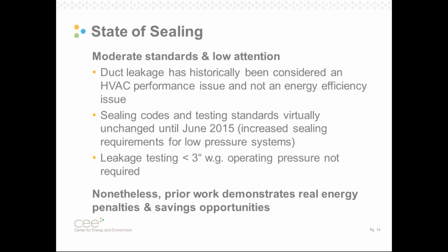Over the last 20 years, codes on duct sealing have changed in little ways, but they generally haven't resulted in much. I can say that the recent code revision in 2015 was probably the most significant change, and that updated code to require sealing on low pressure ductwork, and low pressure ductwork is generally below 2 inches. Medium and high pressure ductwork is above 2 inches and above 3 inches, and that ductwork has always required significant amounts of sealing as well as testing to make sure that leakage is not too severe. Nonetheless, there's been a growing body of literature that suggests that duct leakage, even at low pressures, can have very real energy penalties, and there are savings opportunities.